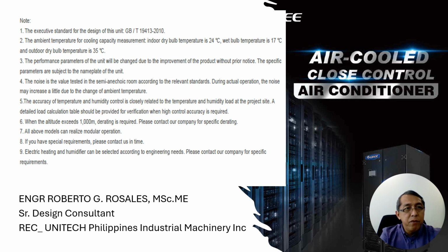Some notes, if you check this on the website: the standard design uses the GB standard 19413, a typical China standard. Remember the ambient temperature for cooling capacity measurement: indoor temperature is 24 degrees C. So if you're designing for lower than 24, for a data center or a CRAC room, please provide the manufacturers the details.